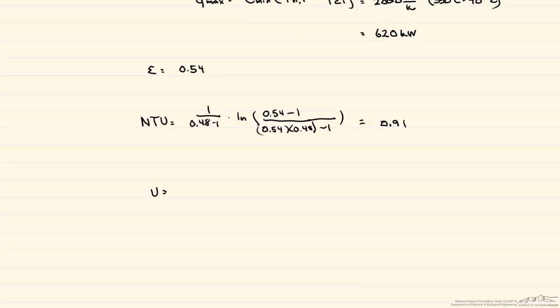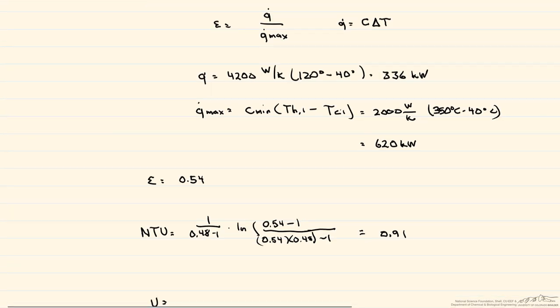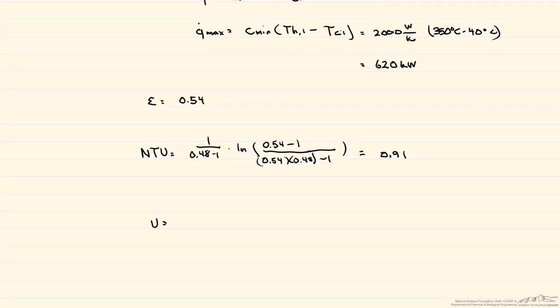And from that, we can calculate the U using the equation from here. Our U is going to be equal to this NTU, 0.91, times our C_min, 2,000 watts per K, divided by our heat transfer area, 20 meters squared. And our U, or overall heat transfer coefficient, equals 92 watts per meter squared Kelvin.